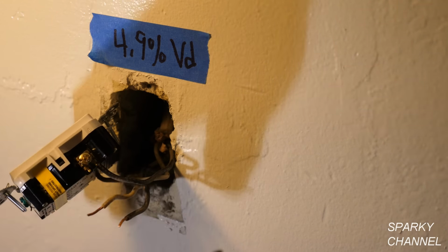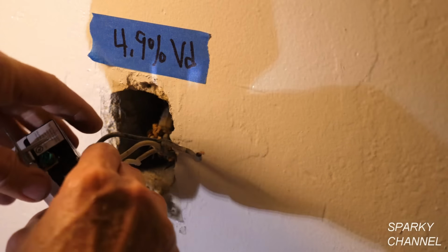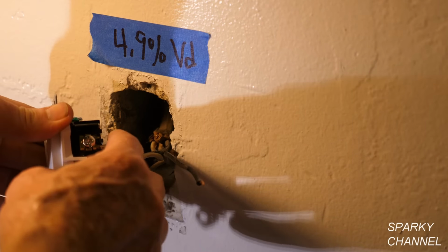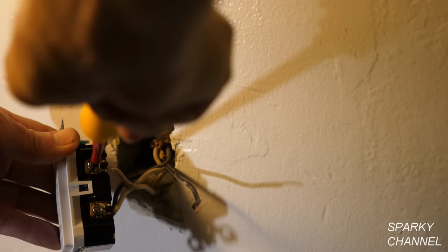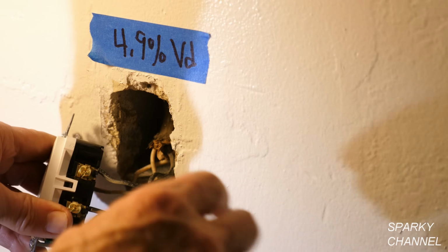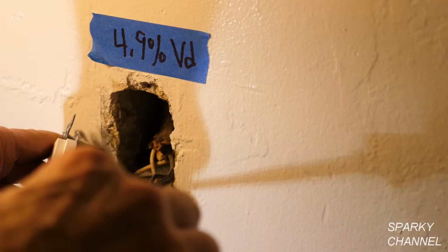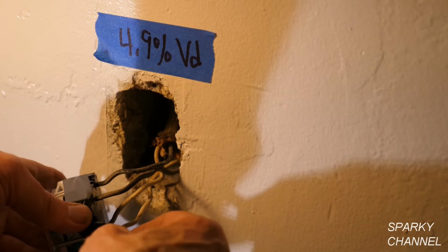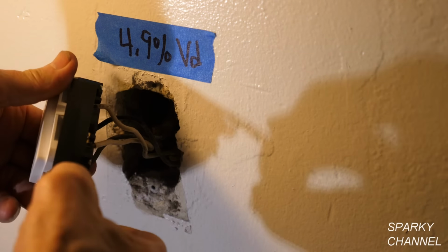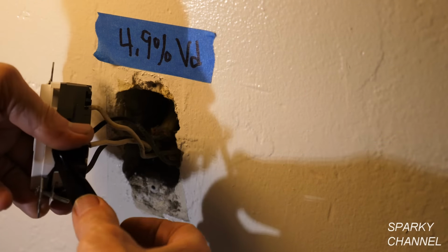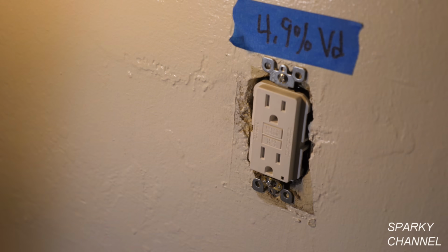Now we take off the yellow tape here. Okay, so put that right in there like that. Here's the hot wire for the load. Okay, got that tightened real nice. I'm now using the green terminal for the ground wire. So just tighten that down. Okay, so our first receptacle is installed, the GFCI.